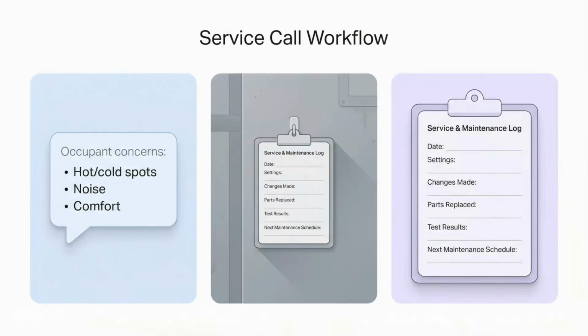Before servicing, the module recommends talking with occupants. They're often the best source of symptoms like hot and cold spots or comfort complaints. After the work, create or update a service and maintenance log and leave it in the mechanical room. Recording original settings, changes, and parts replaced makes future troubleshooting faster and supports a preventative maintenance schedule.